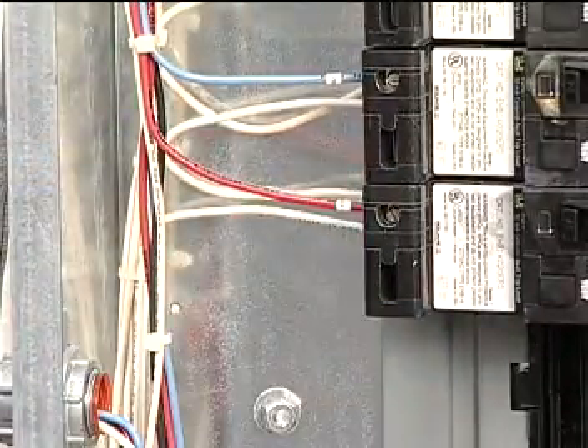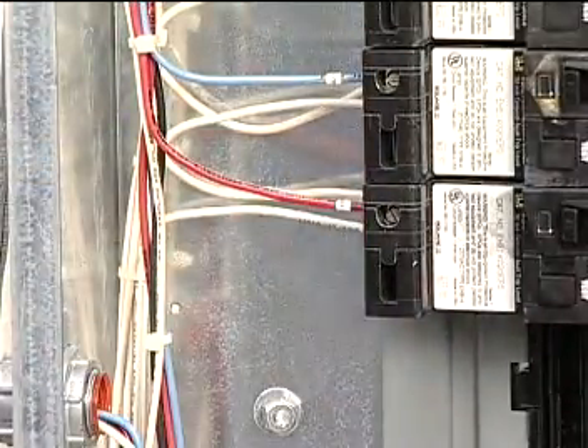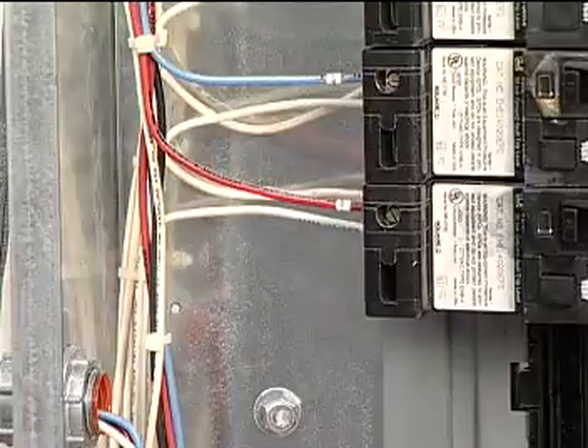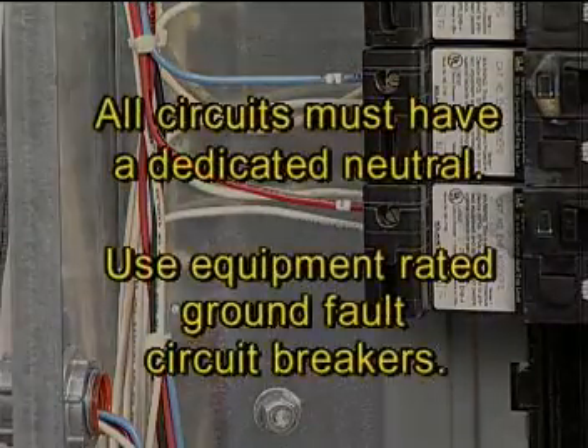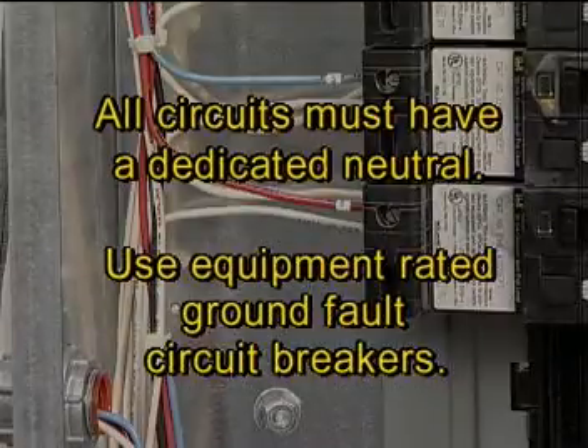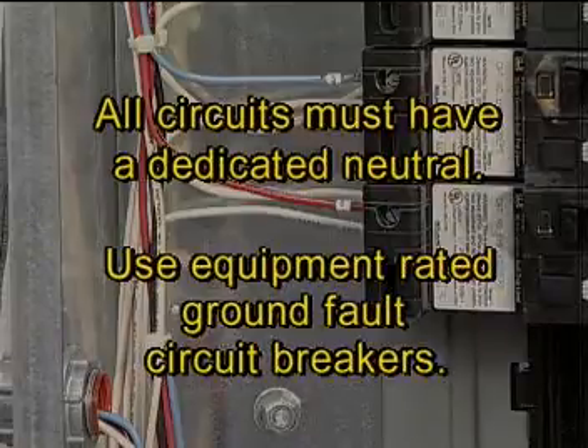The phase and neutral or phase-to-phase branch wires are landed on the circuit breaker terminals. This ensures the ground fault breaker's electronic tripping mechanism has power to operate. Neutrals may not be shared when using ground fault breakers, so all circuits must have a dedicated neutral. Use equipment-rated ground fault circuit breakers. These trip at a higher ground fault current of 30 milliamps, reducing the likelihood of nuisance tripping.